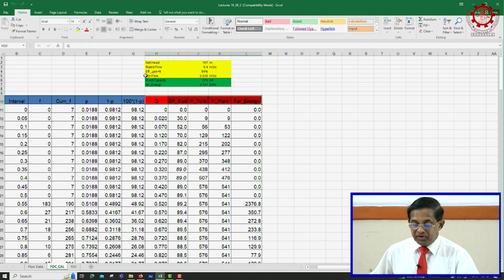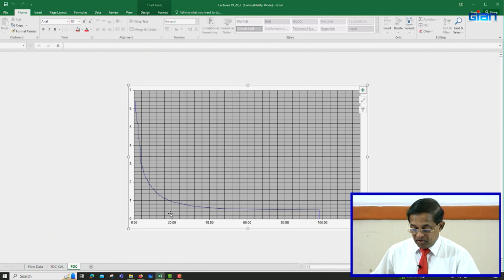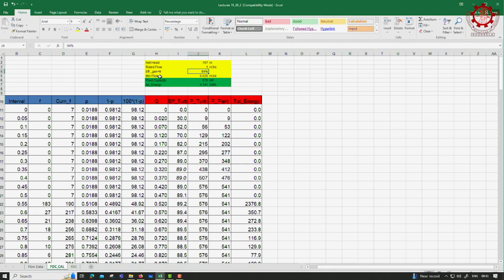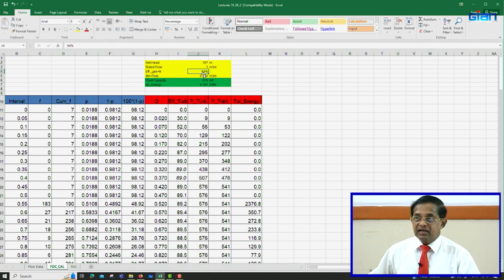I have put the net head. Net head is something we have got already, because we know the gross head, we know the head loss in the penstock, and after deducting it we have got the net head here. I have put it as a typical value, 157. Rated flow I have put as 0.4. It does not matter, you can select whatever you like. I have here selected 0.4, or rather let us put it as 2. Then I have put efficiency of the generator and transformer as 94. Normally, as I told you, generators are about 96% efficient and transformers are about 98% efficient. So, combined together, 98% times 96%, about 94% is the total efficiency.